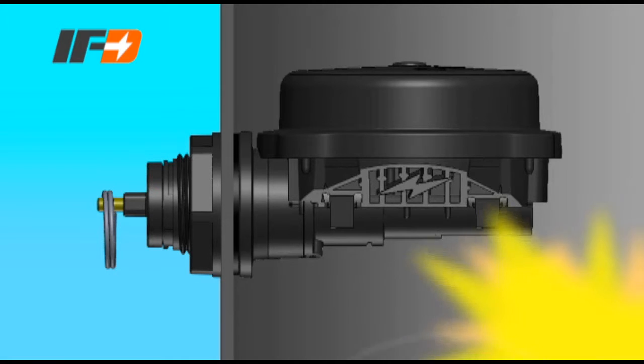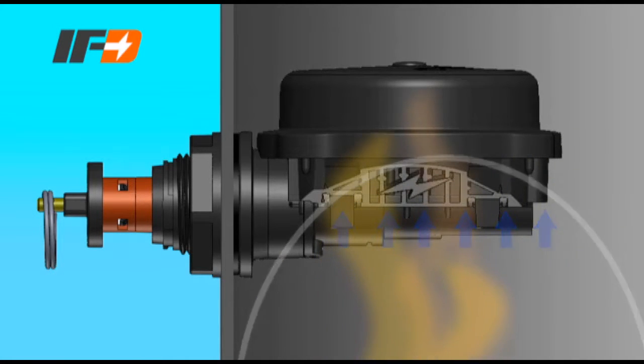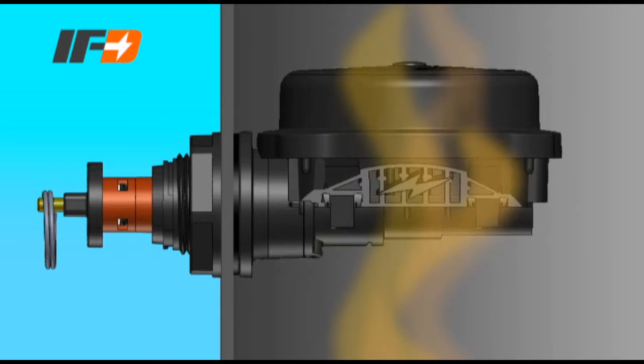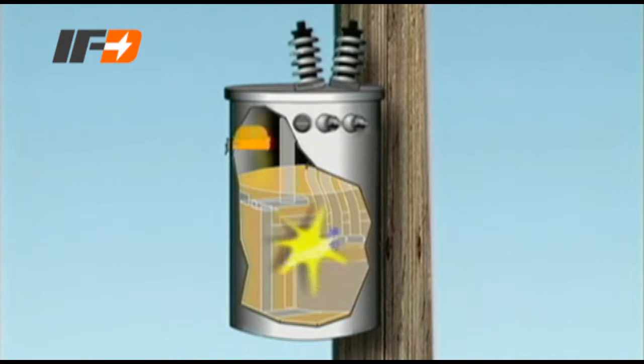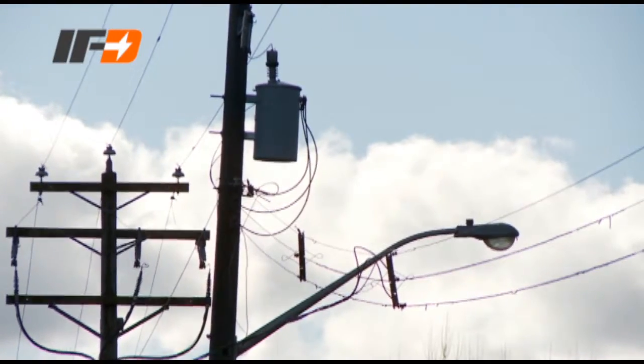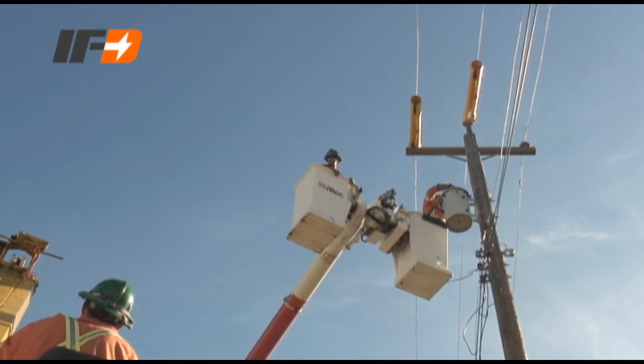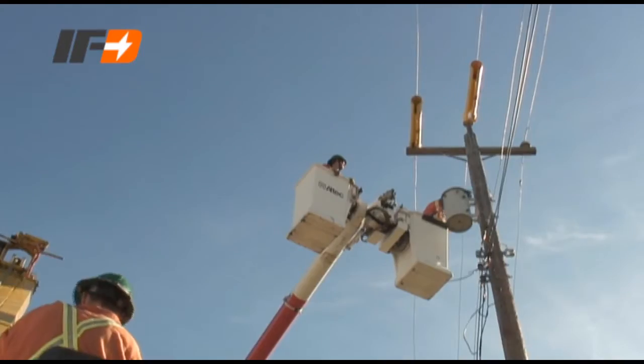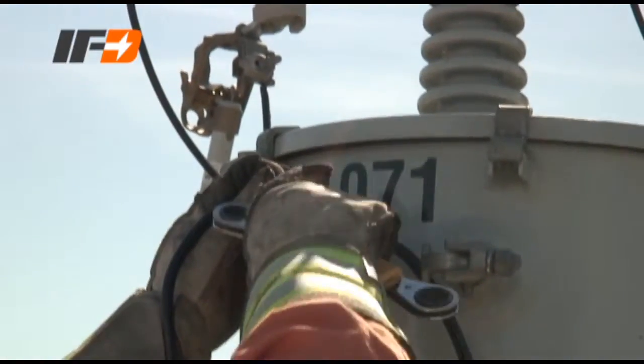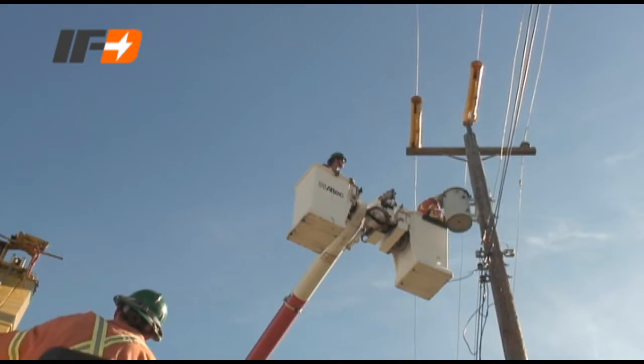When a fault occurs, there is a sudden increase in tank pressure and gases collect in and above the oil. A fault can produce several types of gases that, when mixed in particular proportions, can become explosive. The explosion seen here is an example of one of the hazards line workers may face when re-energizing transformers that have an internal fault. To reduce risk, utilities have developed thorough but time-consuming procedures. Unfortunately, these procedures are not always followed because of the urgency to restore power quickly.